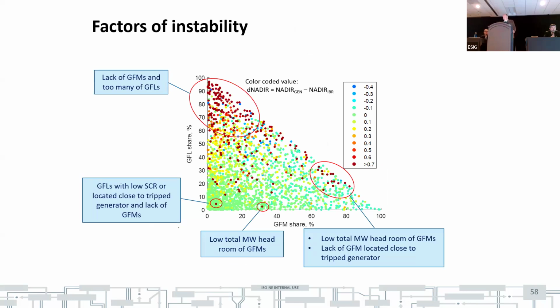This area here shows that despite you have a lot of grid forming inverters, still you may have instability because there is a lack of megawatt headroom for control. And it looks like there are some outliers, like over there. It's a very low percentage of inverters in the system, but you have instability. But that is specifically cases when you have grid following inverters located in a location with a low short circuit ratio.